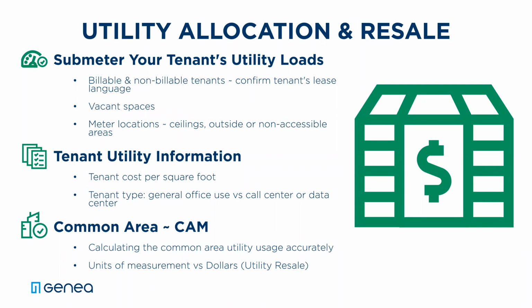And outdoor or indoor meter locations. If you're installing any meters outdoors, you need to make sure that they're outdoor rated meters. And even at that, depending on your location, if you're in California, it shouldn't be a problem. But if you're in Texas or Michigan, where we have extreme weather conditions, you might need to take that into consideration. We had a property that installed the electrical meters on the outside of the building on a retail space. They were outdoor rated meters, but all the meters that were on the south side of the property, after a year and a half, started to fail. And they ultimately ended up replacing all of them due to the weather conditions' impact on them.